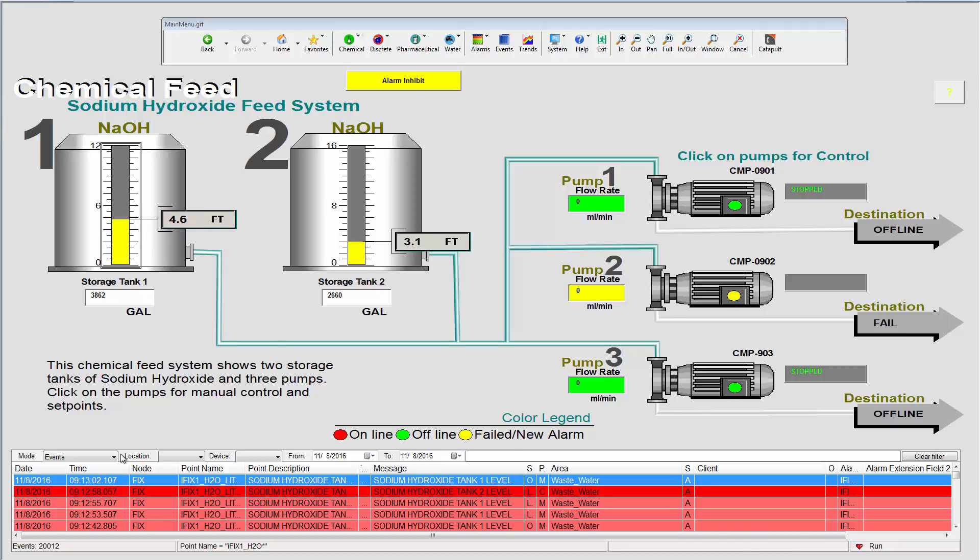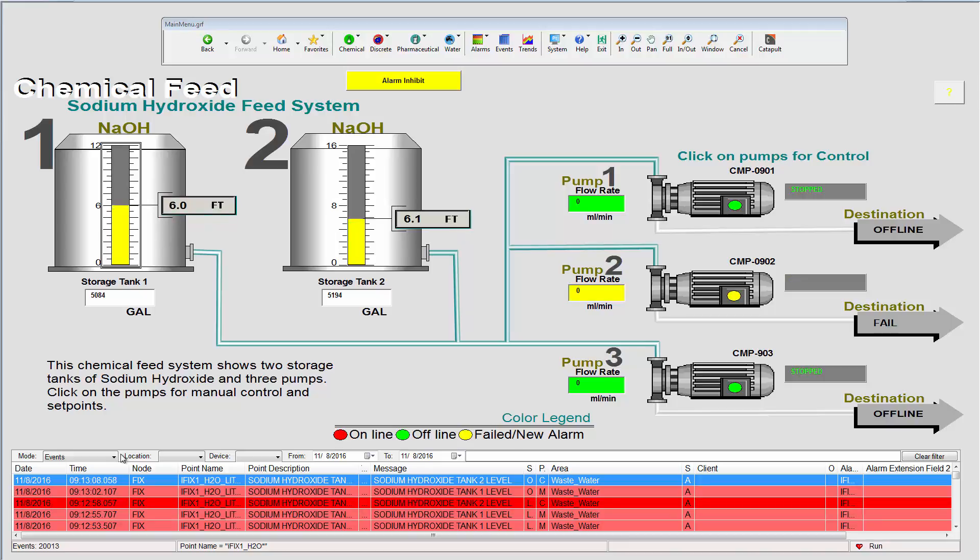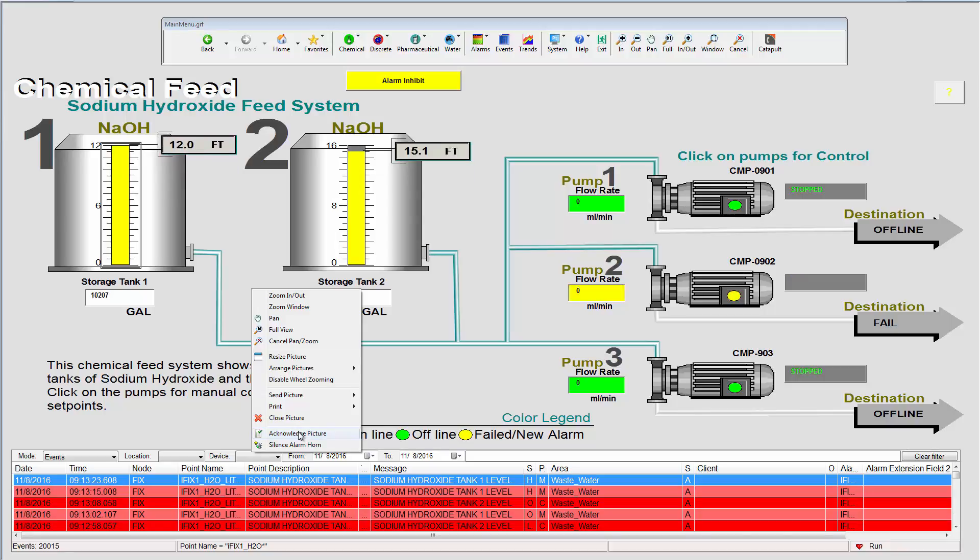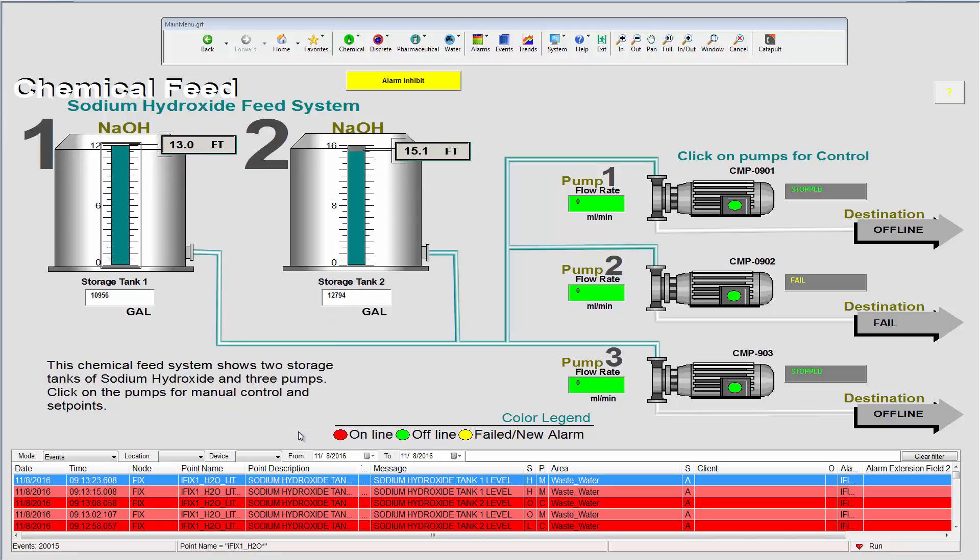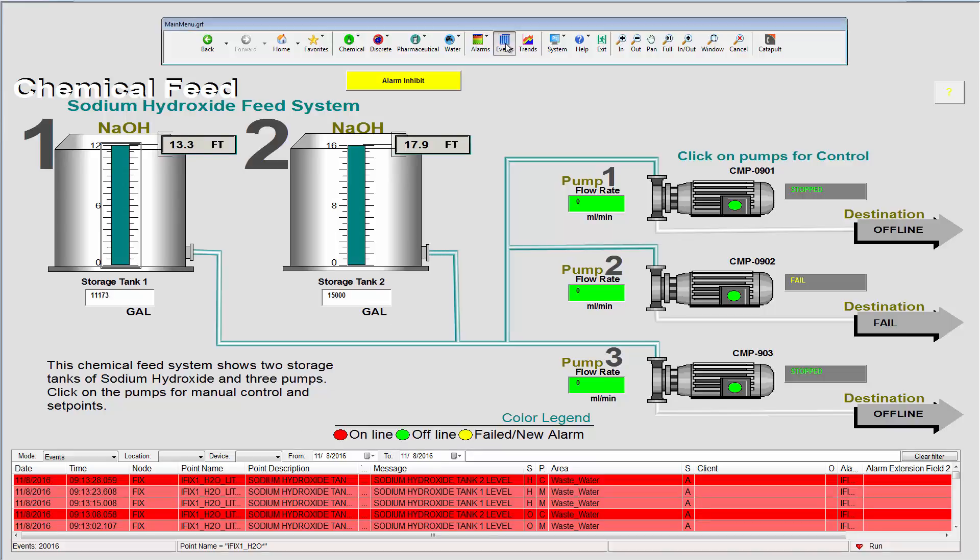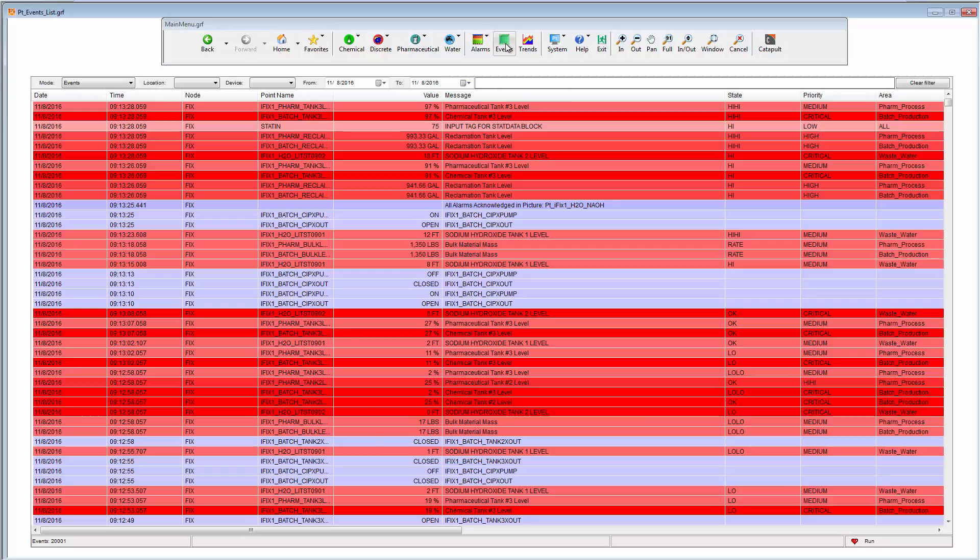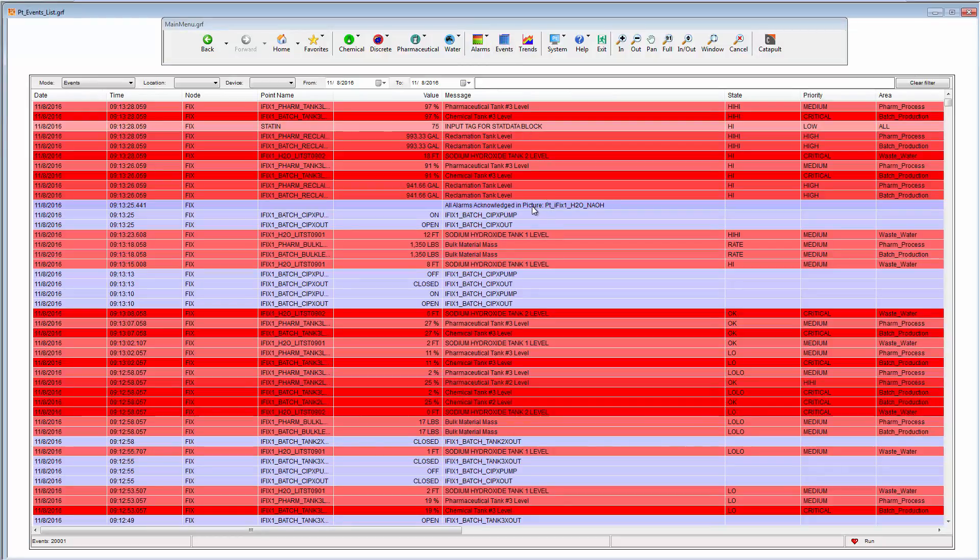For example, if I want to acknowledge all of the alarms on this picture, I can simply right-click to open the new task menu, which is also provided by productivity tools, and use the acknowledge picture option. I can then switch to the main events list, and here we can see that this action has been recorded in the events list.